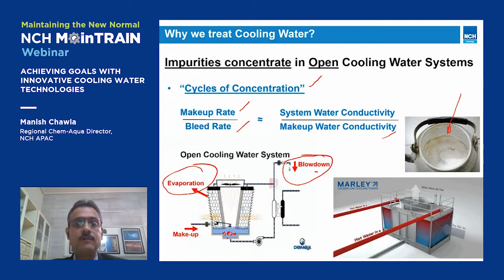It is nothing. Basically, what it means is, if you have makeup water of 100 TDS, and when you test your cooling tower water you find the TDS is, say, 400, then 400 divided by 100 means 4, which means the TDS or the salts got concentrated by 4 times. That is what we call cycle of concentration. It will depend on the ratio of the makeup water rate divided by how much blowdown you gave. The more blowdown you give, the more concentrated water goes out, right? The concentration will fall, the cycle of concentration will come down.